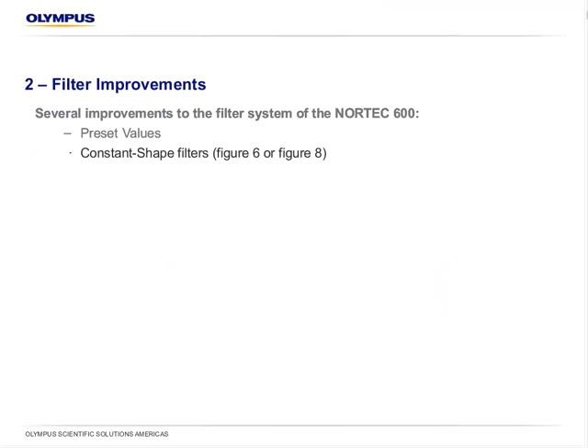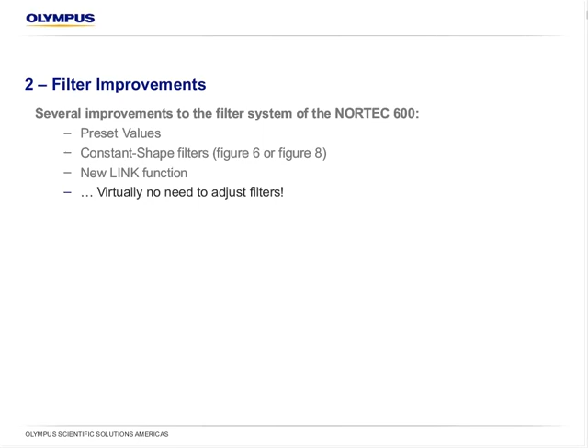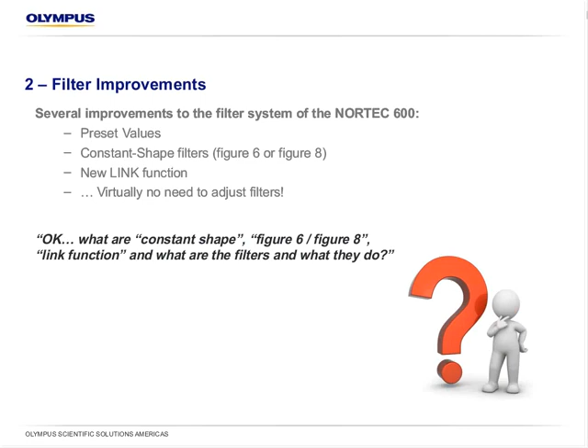Well, you can still adjust the filters, and you might still want to adjust the filters in extreme cases. Let's say if you're inspecting 3 inches diameter, which is 76 millimeter hole, well, maybe the filters might need some tuning, but for the bulk of the work and most of the time, you would not need to adjust those filters. So, you may ask, all right, what is constant shape? What is figure 6? What's figure 8? The link function, and what exactly does the filter do to help me? So, here's some further details.